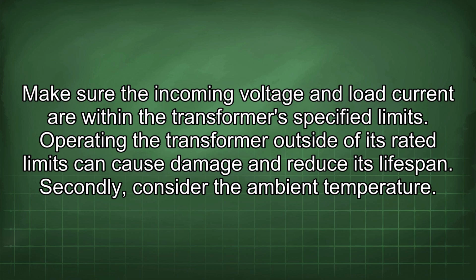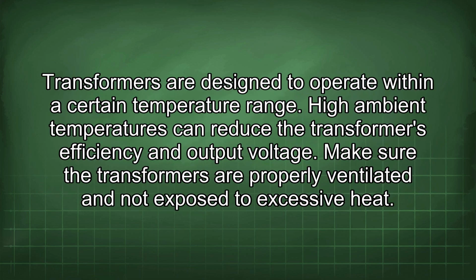Secondly, consider the ambient temperature. Transformers are designed to operate within a certain temperature range. High ambient temperatures can reduce the transformer's efficiency and output voltage. Make sure the transformers are properly ventilated and not exposed to excessive heat.